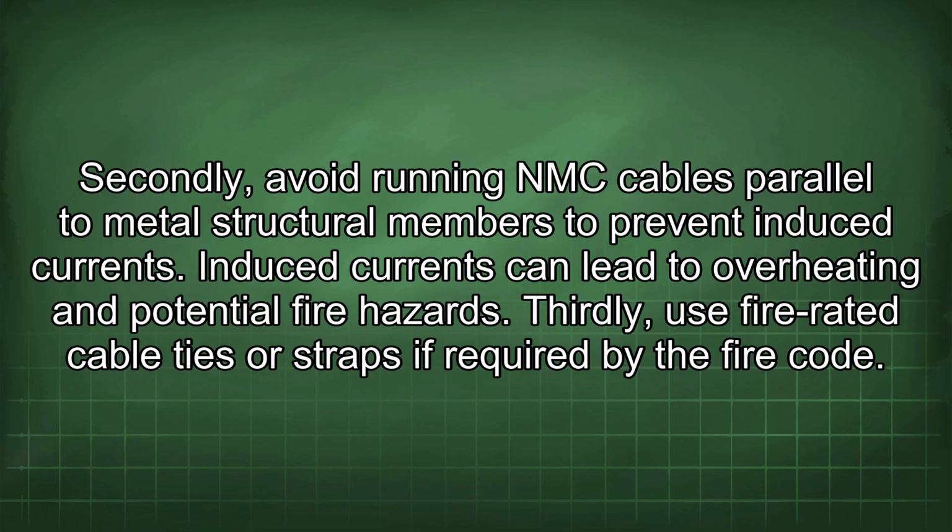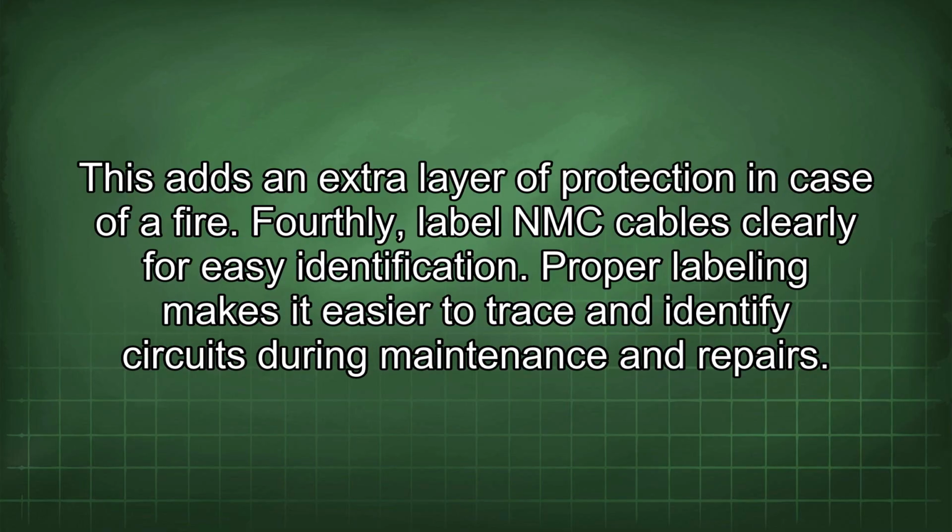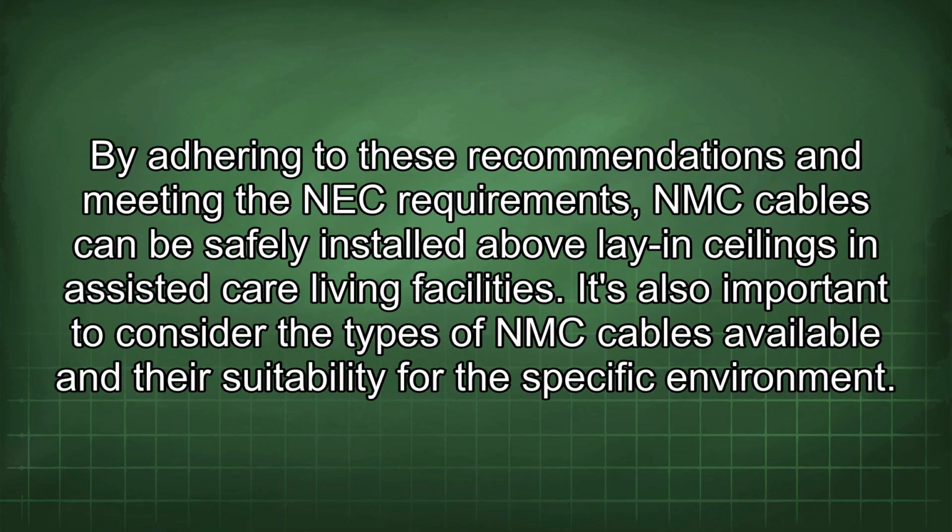Thirdly, use fire-rated cable ties or straps if required by the fire code. This adds an extra layer of protection in case of a fire. Fourthly, label NMC cables clearly for easy identification. Proper labeling makes it easier to trace and identify circuits during maintenance and repairs.